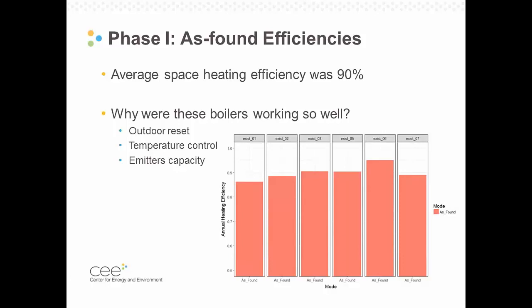These boilers did have AFUE ratings, or rated efficiencies, of 90 to 95%, so maybe we were a little bit below those, but that's pretty typical for field measured efficiencies. Anytime you put something out into actual use, the conditions change a little bit from that ideal lab condition, so you always see a small reduction. So this 90% efficiency number is really quite a good result, and that's right in line with what we'd expect to see, the 12 to 15% energy savings across the board, and we'll talk more about those energy savings as we move forward.